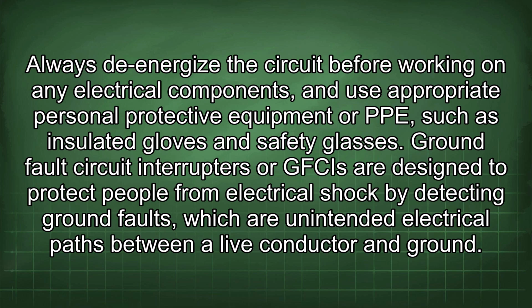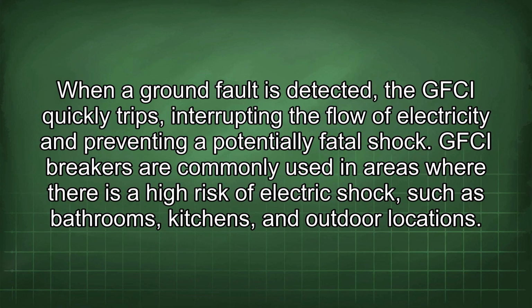Always de-energize the circuit before working on any electrical components, and use appropriate personal protective equipment, or PPE, such as insulated gloves and safety glasses. Ground fault circuit interrupters, or GFCIs, are designed to protect people from electrical shock by detecting ground faults, which are unintended electrical paths between a live conductor and ground. When a ground fault is detected, the GFCI quickly trips, interrupting the flow of electricity and preventing a potentially fatal shock.